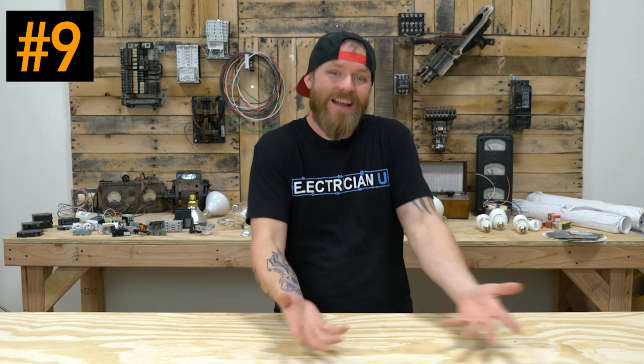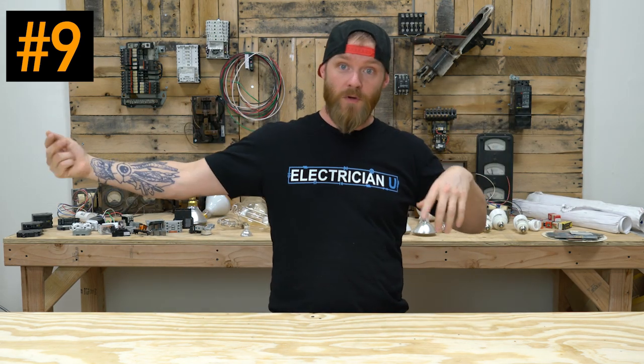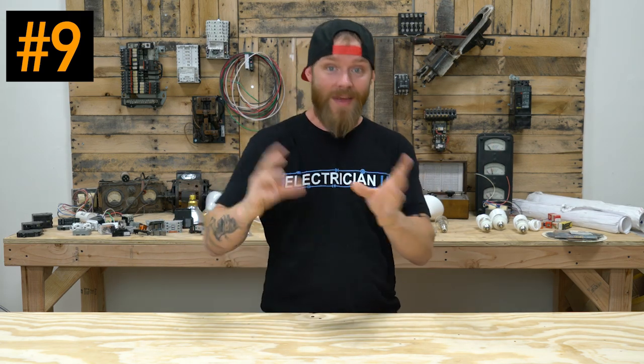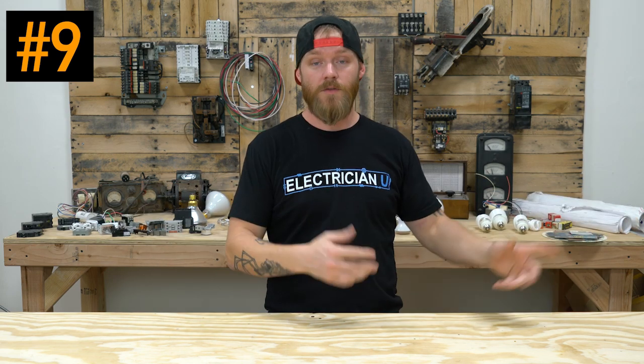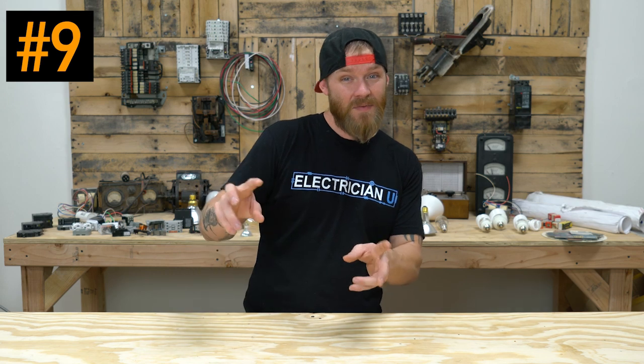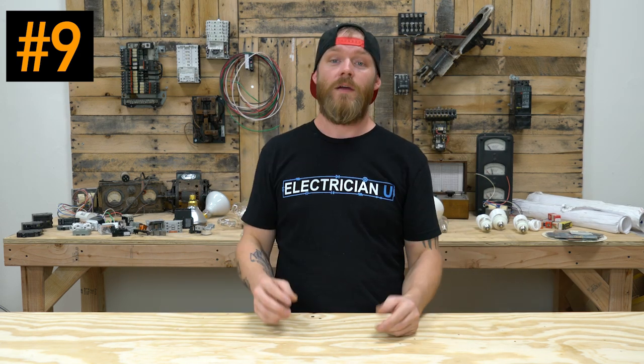Number 9 on our list is a raceway. So a raceway generally just means a piece of conduit or tubing. It can be a gutter, like a metal box that has a removable cover, but it's anything that is an enclosed channel of some sort that is specifically designed to hold conductors or cables or bus bars. So, metal gutters that have a removable cover, you're bringing conductors through that. You can even put little bus bars inside of them. That is a raceway. A piece of EMT conduit, you run conductors through it. That is a raceway. There are some enclosures that classify as raceways and some that you cannot use as raceways. There are places where you can't use an electrical panel for a raceway. But anything that's specifically designed to house cables, conductors, or bus bars is a raceway.